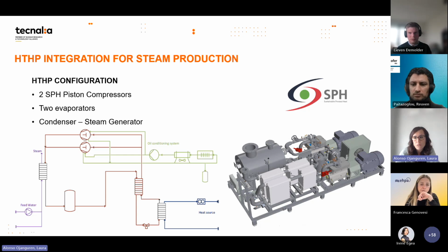So this goes directly to the condenser of the heat pump, where heat is exchanged with refrigerant coming from both compressors, and so the condenser condenses the refrigerant, but it is also a direct steam generator. And this is a plate and shell heat exchanger. They have as well an oil conditioning system, and, also not represented in the figure, a subcooler is included for increasing the efficiency, and this will preheat the feed water before going to the steam generator. There is variable speed control for the compressors, and this heat pump is operating with a low global warming potential synthetic refrigerant.